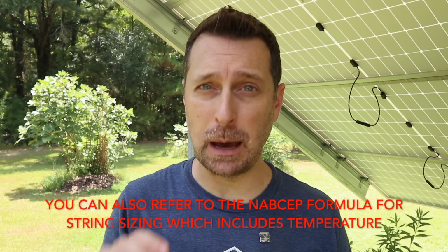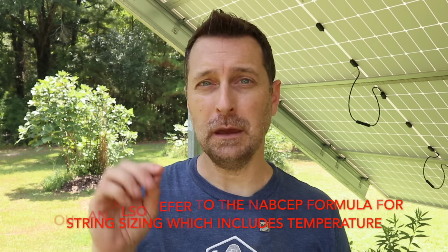So the recommendation is, for each string that you put together for each MPPT on the FlexBoss 21, each inverter is going to be different, that you stay 10 to 15% under the max voltage. So for larger inverters like this, you do need a decent amount of panels to run them properly. And if you're right on the edge and you lose a little efficiency over time, they're not going to work. And that's what happened in our case, so make sure you pay close attention to that.